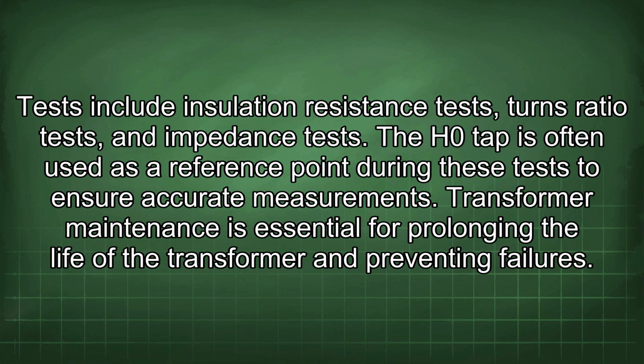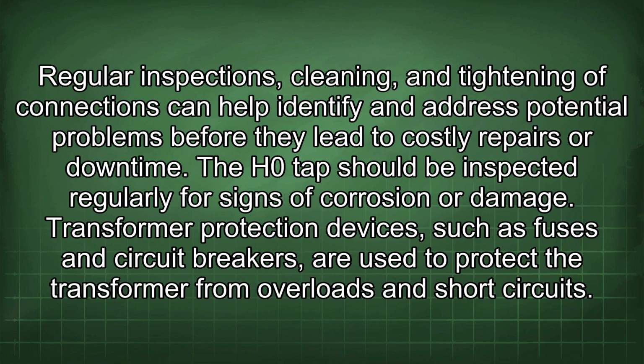Transformer maintenance is essential for prolonging the life of the transformer and preventing failures. Regular inspections, cleaning, and tightening of connections can help identify and address potential problems before they lead to costly repairs or downtime. The H0 tap should be inspected regularly for signs of corrosion or damage.